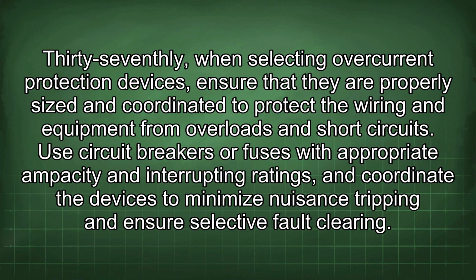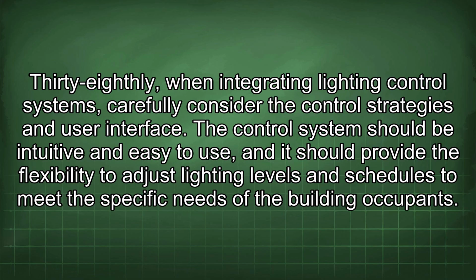37thly, when selecting overcurrent protection devices, ensure that they are properly sized and coordinated to protect the wiring and equipment from overloads and short circuits. Use circuit breakers or fuses with appropriate ampacity and interrupting ratings, and coordinate the devices to minimize nuisance tripping and ensure selective fault clearing. 38thly, when integrating lighting control systems, carefully consider the control strategies and user interface.